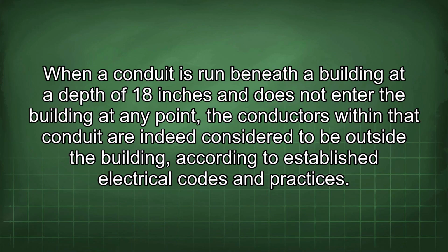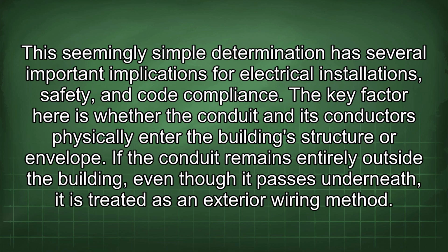When a conduit is run beneath a building at a depth of 18 inches and does not enter the building at any point, the conductors within that conduit are indeed considered to be outside the building, according to established electrical codes and practices. This seemingly simple determination has several important implications for electrical installations, safety, and code compliance. The key factor here is whether the conduit and its conductors physically enter the building's structure or envelope.